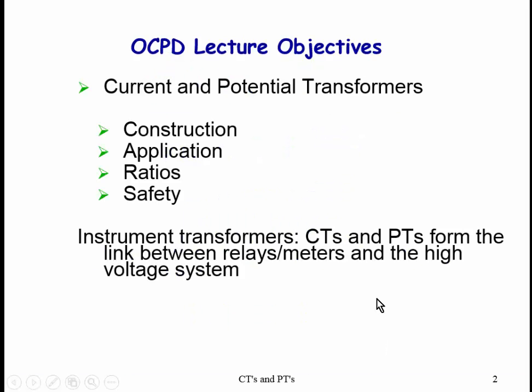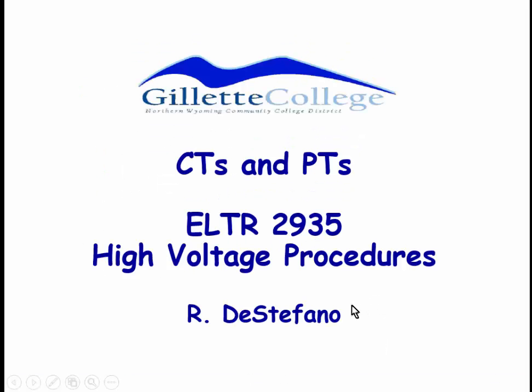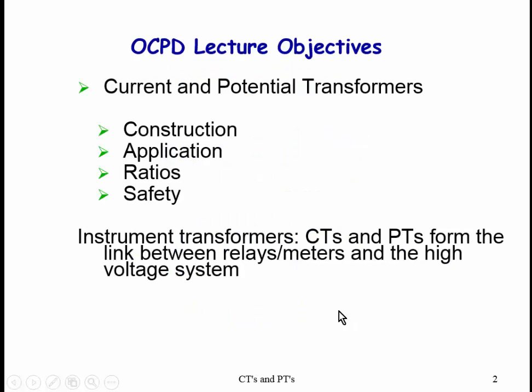CTs and PTs, that would be instrument transformers if you group them together. And we're going to look at how they're built and how to apply them. This is the equipment that is going to connect a high voltage system to the meters and relays that we use to work with the system. So it's a safe way to link high voltage with essentially low voltage equipment.